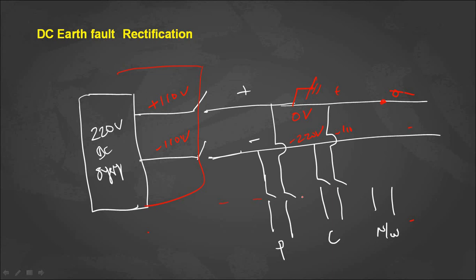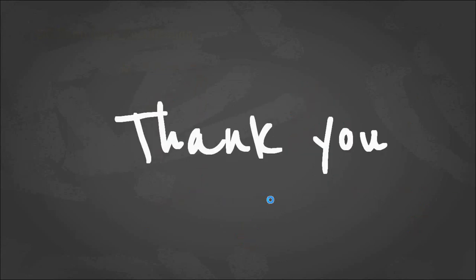If the DC bus bar itself is grounded — for example due to a broken insulator — the positive bus bar voltage becomes 0 volts and the negative bus bar voltage becomes -220 volts. We turn off all MCBs; even after doing so the abnormal voltage remains, confirming the bus bar itself is grounded. We then inspect the bus bar insulators, identify the damaged one, and replace it with a healthy insulator. By this process of sectionalizing, we can identify and rectify the DC earth fault in a DC system.